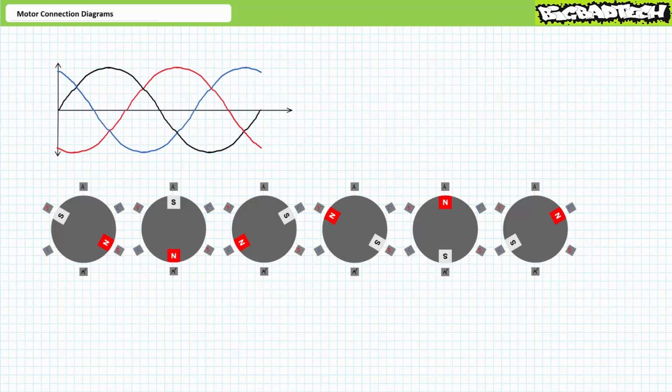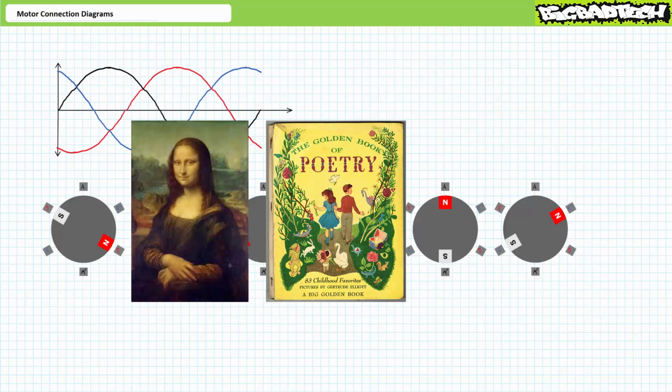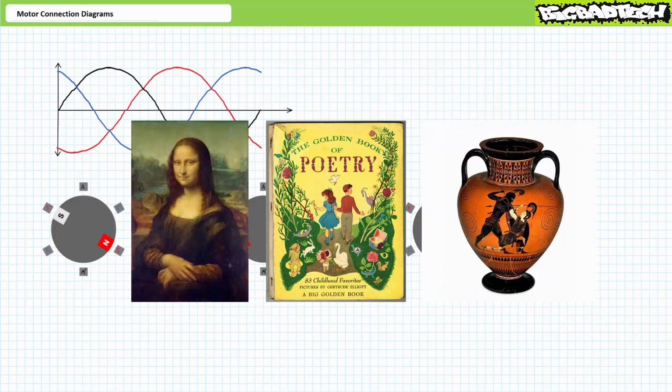Bottom line up front, motor connection diagrams aren't paintings, poems, or pottery to appreciate, critique, or interpret as you see fit, and you get 0 points for creativity. Follow the connection diagrams exactly as illustrated, otherwise you'll hurt the motor, your instruments, or yourself. An improperly wired motor might be damaged, or at the very least, not work well.